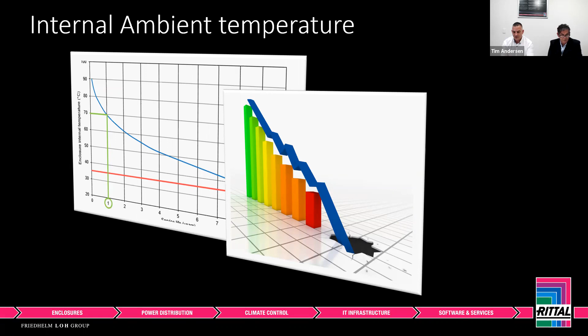On the opposing end, we want to dissipate or reject heat. Again, there are two methods of doing this. Passive dissipation, this is thermal radiation or convection heat dissipation. This occurs naturally through the heat radiated through the enclosure material. Then there is also active cooling, and this is where we introduce some of the Rittal products to aid with pushing out some of the hot air in favour of cooler air. Rittal has a vast selection of products to do this, and as you can see, there are fans, cooling units, liquid cooled packages.